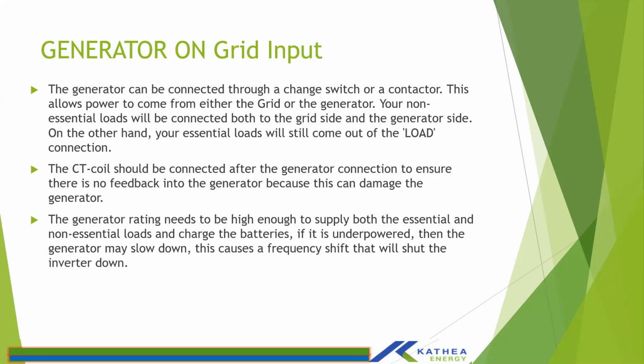Not taking into consideration that when an inductive load starts up, it would draw in rush current up to 6 to 10 times. So whenever you're using a generator, you can use an average of ×5 the size of it when you're using an inductive load to spec your system. Because whenever you have a changeover from grid to UPS mode, that's in most instances where the inverter trips, whether it's a SunSynk or what inverter.